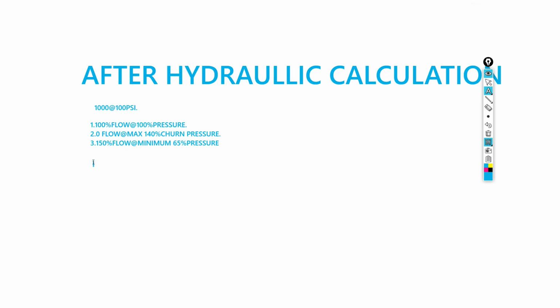Okay, so this is the limit. We all know the limit of selecting a fire pump: the system demand should fall between 90% to 150%.